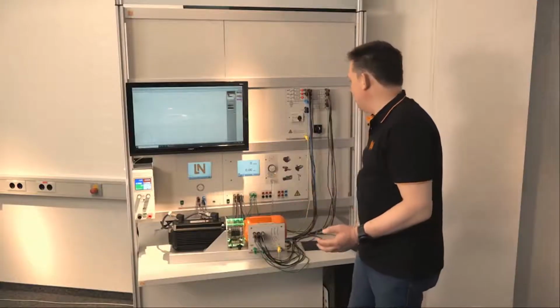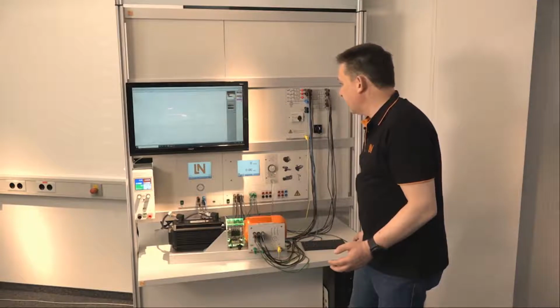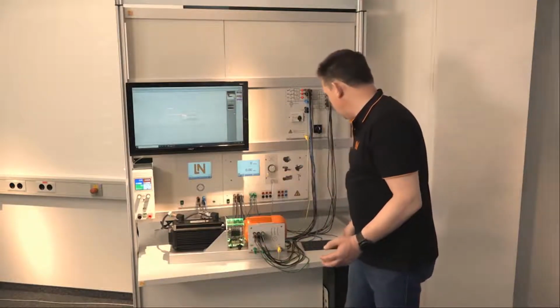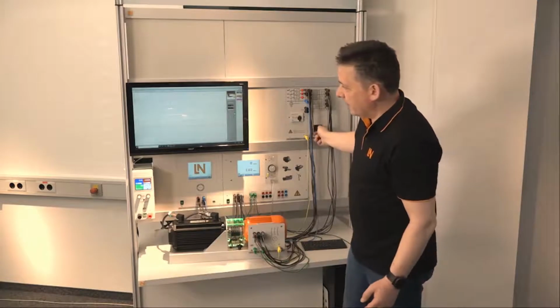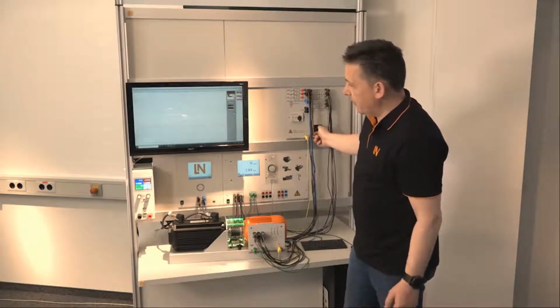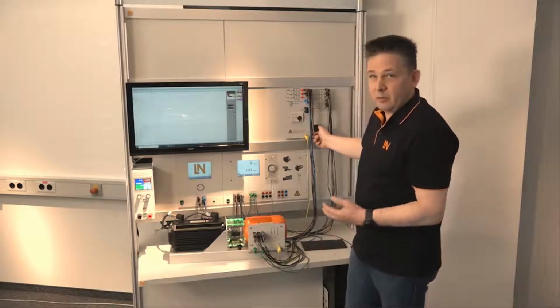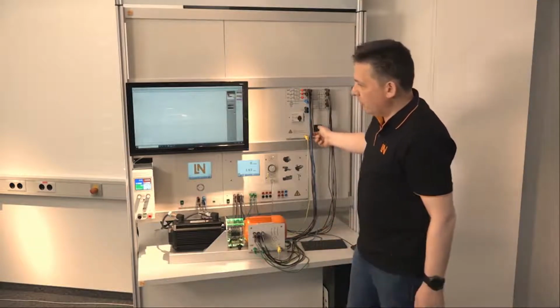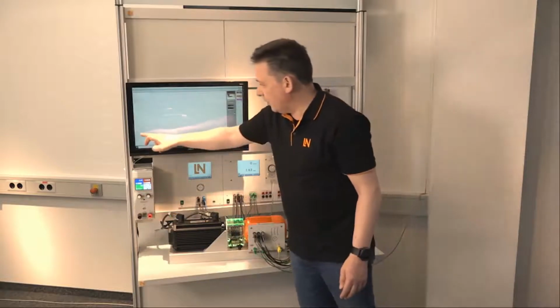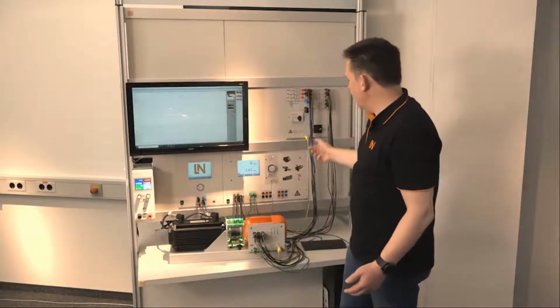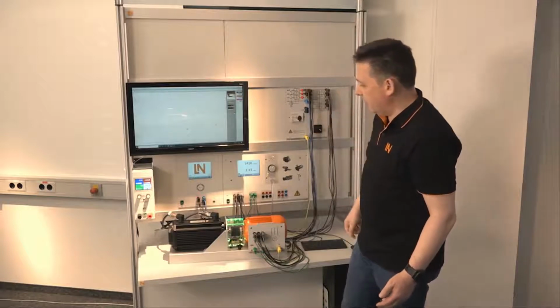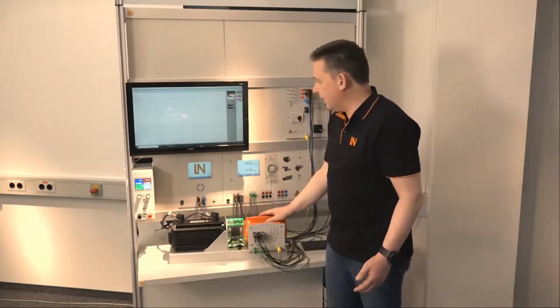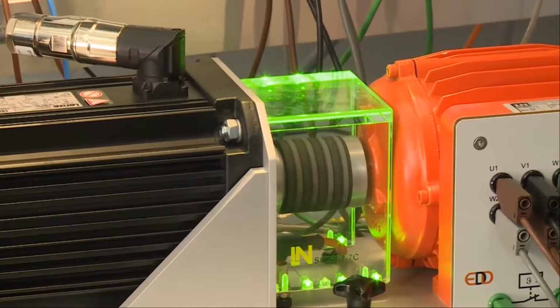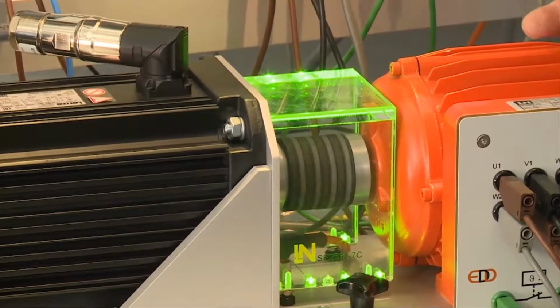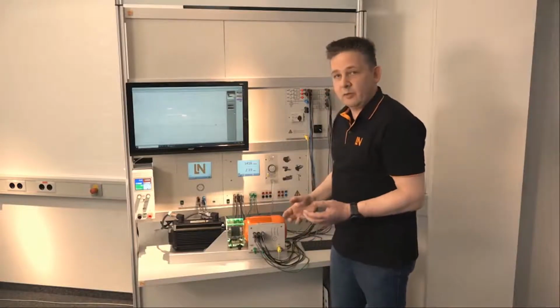And now I try to run the motor with the star-delta switch. I enable the load, press OK, start the Y circuit or star circuit, and nothing happens. The motor couldn't start. There's not enough torque to start. We see the working point is at this point and no turning of the motor. If I go to delta, the motor is turning. So for this special machine, star-delta is not working.